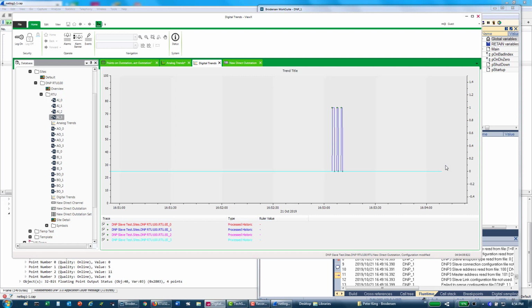So we still expect a Class 1 event to go straight away, but we expect a Class 2 event to, if I only make 2 changes, we will have to wait until the 30-second event poll occurs. Now we're currently at 25, 26, so we'll not find out about those Class 2 events until the event poll occurs.